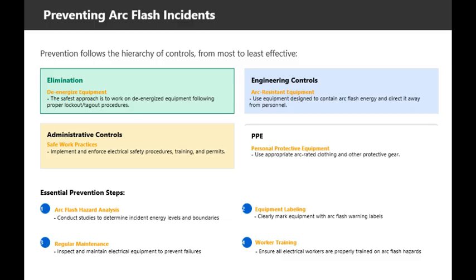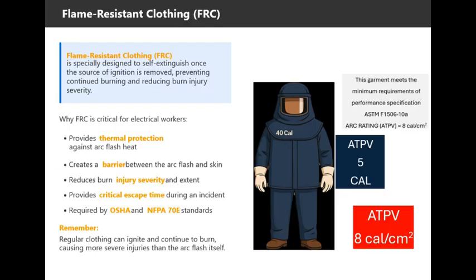Essential prevention steps include conducting arc flash hazard analyses to determine incident energy levels and boundaries, properly labeling equipment with arc flash warnings, maintaining regular inspection and maintenance schedules, and ensuring all electrical workers receive proper training on arc flash hazards. The key message here is that prevention requires a systematic approach. It's not enough to just wear PPE, we need to implement all levels of the hierarchy to effectively manage arc flash risks. Now let's turn our attention to flame-resistant clothing, or FRC.